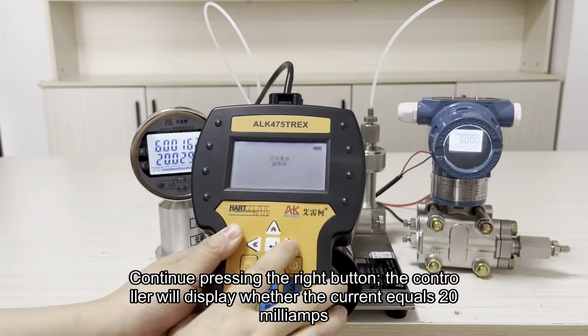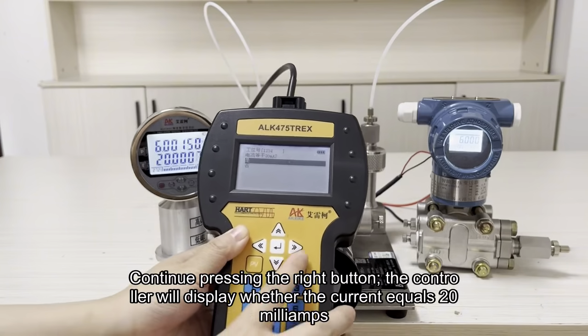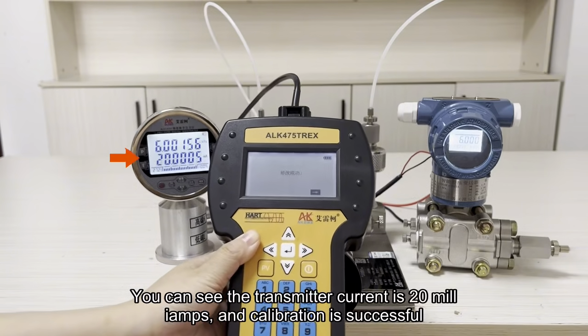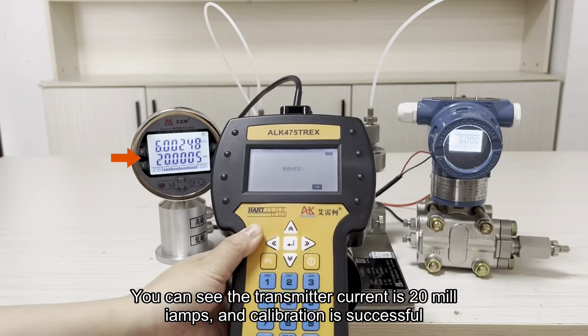Continue pressing the right button. The controller will display whether the current equals 20 mA. Finally, right-click to select. You can see the transmitter current is 20 mA, and calibration is successful.